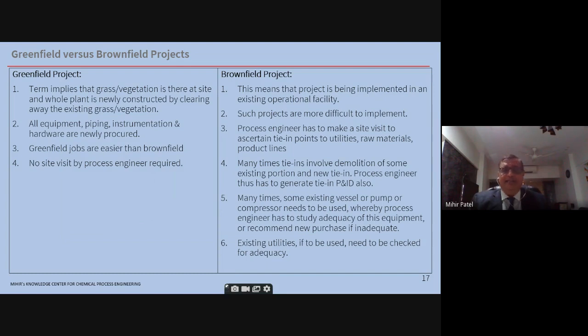For example, in the P&IDs, for a brownfield job, you may have to tie up to the existing utilities, etc. Firefighting network one has to tie up with. So all these have to come in the P&ID. So there is a demolition P&ID as well as a new P&ID for the new tie-in point. Plus in the brownfield job, some existing vessel or pump may have to be used. So the adequacy of that existing vessel or pump has to be checked. For example, the existing flare system needs to be used. So that existing flare system adequacy needs to be checked. So there are many more complications in a brownfield project as compared to a greenfield job.